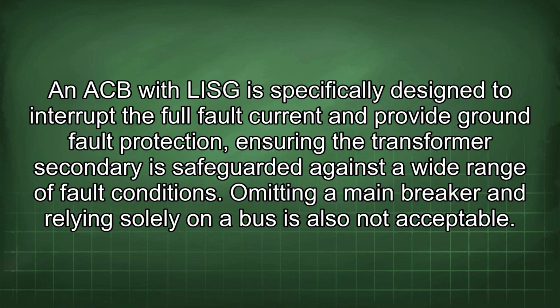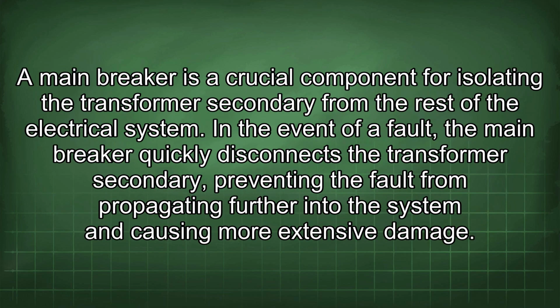Omitting a main breaker and relying solely on a bus is also not acceptable. A main breaker is a crucial component for isolating the transformer secondary from the rest of the electrical system. In the event of a fault, the main breaker quickly disconnects the transformer secondary, preventing the fault from propagating further into the system and causing more extensive damage.